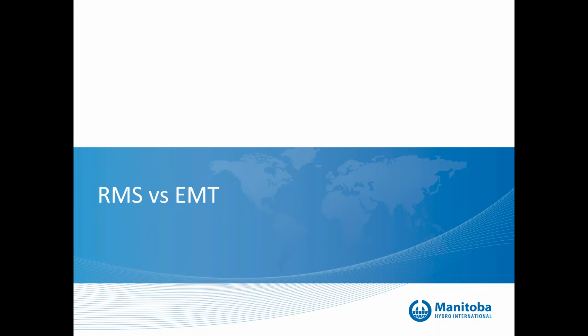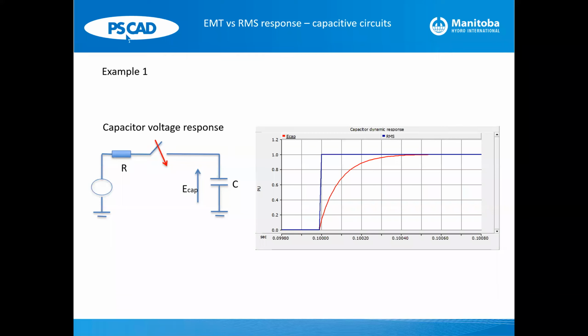I will spend a few minutes discussing some examples, comparing RMS with EMT programs like PSCAD. So the most basic example I can illustrate to you is an RC circuit like this, where if you close the breaker, in RMS you'll just see a switch. The voltage across the capacitor will go from 0 to 1 in an instant, okay? However, due to the dV/dt characteristic of the capacitor, you see a response like this in EMT. So that's at the very high level.